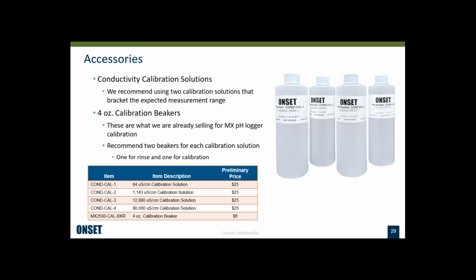So, calibration solutions for the conductivity sensor. We're going to be selling the 4 different values. They're all $25 in US, and I mentioned the beakers. I do recommend, for doing the calibration, you should have a pre-rinse beaker for rinsing it off before you put it in the final beaker for the calibration. And so for that reason, I recommend having 2 beakers for each calibration solution. So if you're doing calibration at 2 points, you should have 4 beakers to do the proper rinse and calibration.